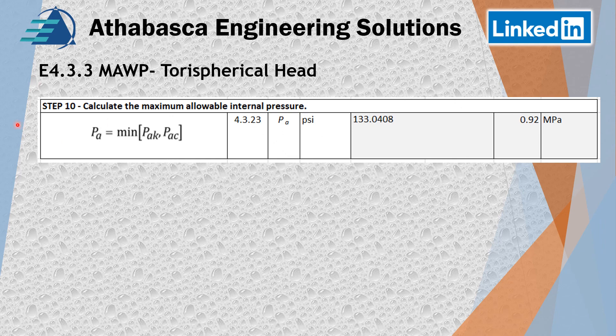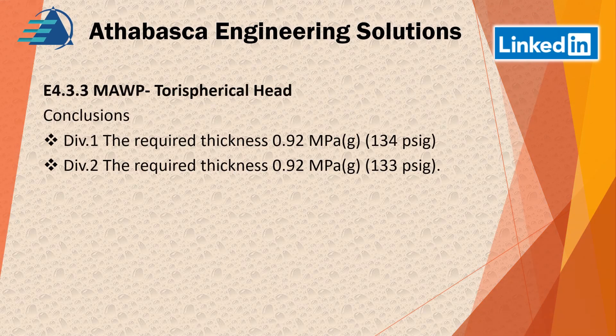In step ten we take the minimum of these two values and determine it to be 133 PSI. What can we conclude? We went through Division 1, which was a lot simpler — especially if you use an ASME head, which I would recommend. Head vendors I've dealt with would only use that anyway, and your stresses are basically going to be the same — just a little rounding error. What was also interesting from the detailed Division 2 calculation is that the weakness is in the knuckle, not in the crown, which is what we would expect.